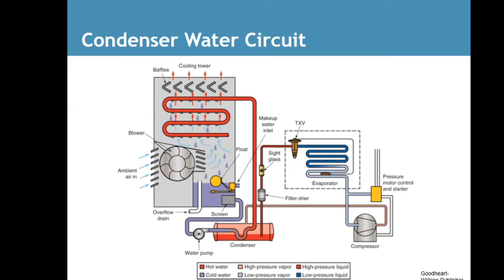Here's a water-cooled condenser circuit. This is like any other air conditioning system. It just uses water rather than air. A few things that I'll bring out: unlike this system, there is a cooling tower that uses a drip system at the top. At the bottom right-hand side of that large piece, you'll see that blue section that has the yellow float ball in it, and this is the makeup water. So anytime the system starts losing water from evaporation, it needs to be replaced, and this is an automatic system that keeps that water reservoir full for cooling the system.